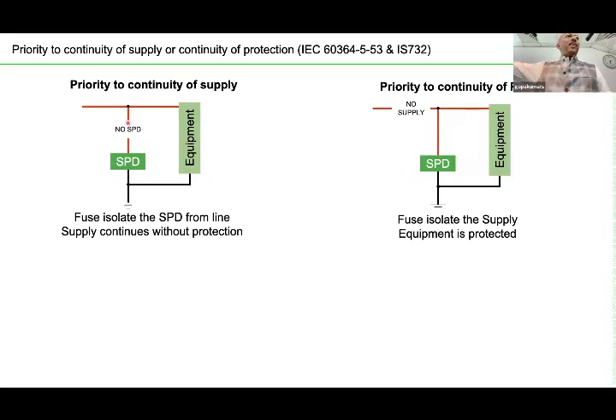The next lightning, your equipment will burn. You cannot afford to lose the equipment. For highly sensitive equipment, if you cannot afford the failure of such equipment, you should go for the second one. You should give priority to continuity of protection. Continuity of protection, in the sense, the SPD is in shorted condition. It's internally shorted, so your line and neutral are connected. So there is no conducted surge into your equipment. Your equipment is protected.